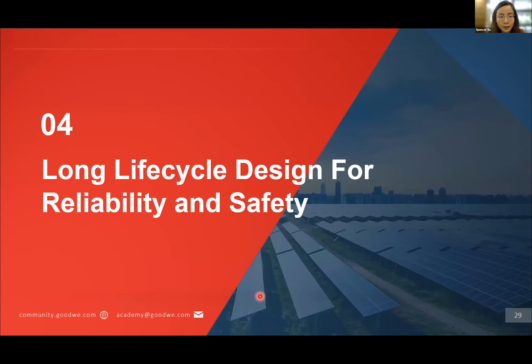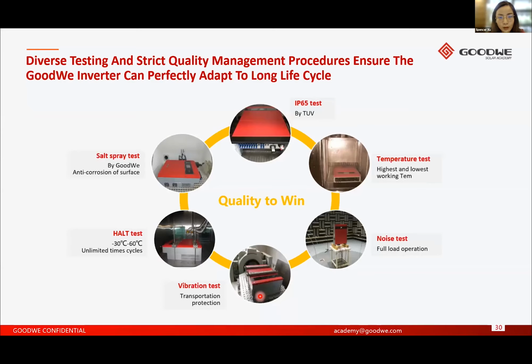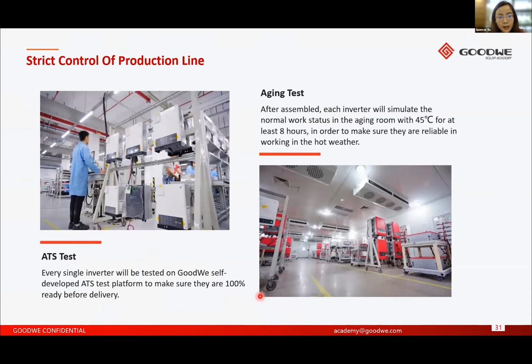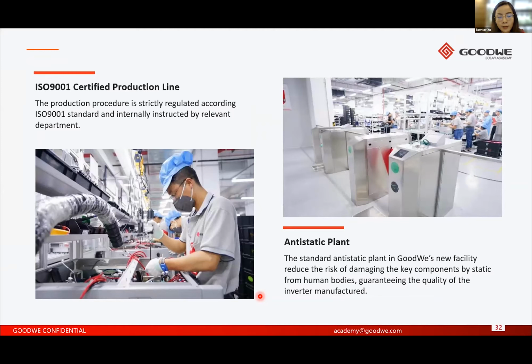Well, now let's have a look at how GoodWe inverters ensure reliability and safety. On one hand, we have diverse tests, either internally or externally via third-party institutions. For example, the IP protection test is conducted by TUV. And on the other hand, we also have a strict quality management procedure in the factory. Here, as you can see through the pictures, we have strict controls on our production lines. We have self-developed ATS tests to make sure that our inverters are 100% ready before shipment. Aging tests also ensure our inverters are reliable in extreme hot weather conditions. Our production line is regulated according to ISO 9001. And we also have a standard anti-static plant to reduce the risk of static from human bodies.